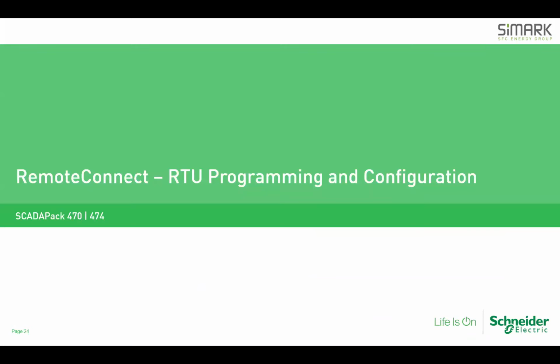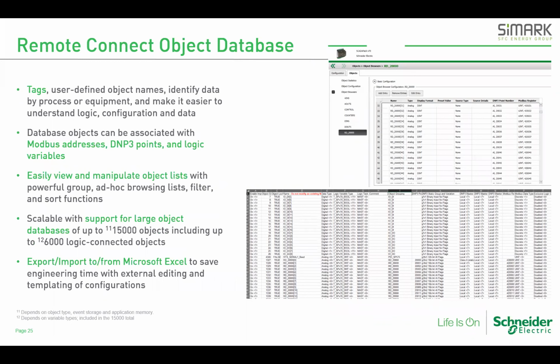These RTUs, along with the existing 574, 575, and 570 - all of the X70 series - are configured using the new Remote Connect programming and configuration software. This software uses object names or tags to define where you'll store your program code information. Each object can be given either a Modbus or DNP3 address to allow a remote host to extract the values contained within the object. So all communications between the RTU and an HMI or SCADA host are done using DNP3 or Modbus protocol, not the object name. Use of the object names is limited to within the controller.